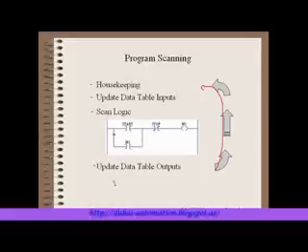This is called the PLC program scan, and a PLC program will scan repetitively as it's running and constantly update its outputs and constantly check its inputs, and that's the important thing to remember about programming in a PLC. PLC program scans are very quick. You will see them on the order of milliseconds and microseconds. So we're looking at information that's being processed very quickly, and it obviously has to be able to monitor relays, encoders, and other fast-acting devices out in the field.